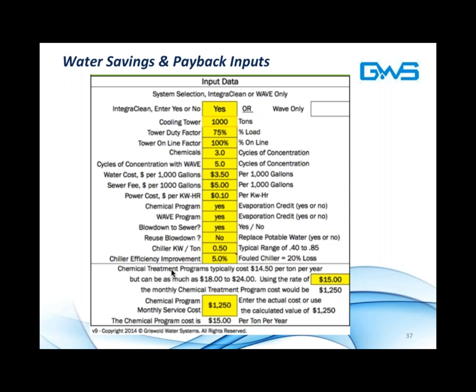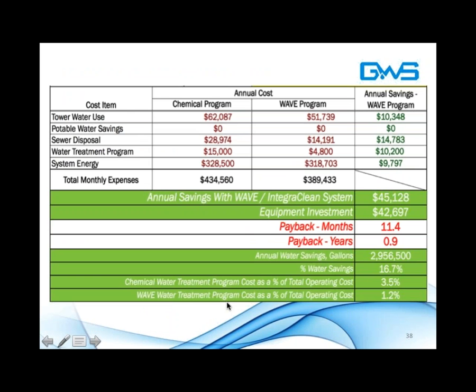Water cost in this part of the world is approximately $3.50 per 1,000 gallons, and the discharge costs, which are often double that of the purchase costs, in this case are $5 per 1,000 gallons. So you can see discharge is very expensive in these regions. We compare the average service cost of a system here for chemicals, and you can see quite quickly that the payback is significant. Down here in the green, annual water savings show approximately 3 million gallons, or 16.7% in this case, simply by increasing 2 cycles of concentration.